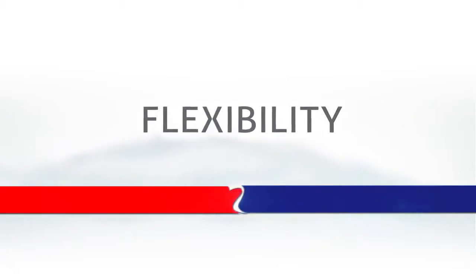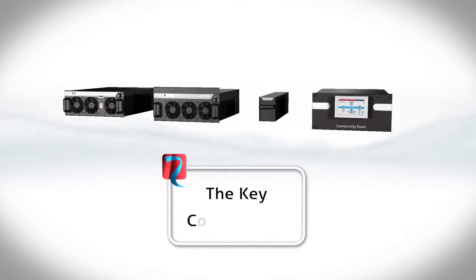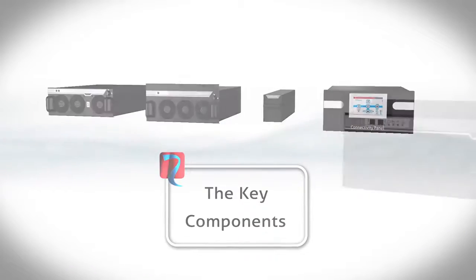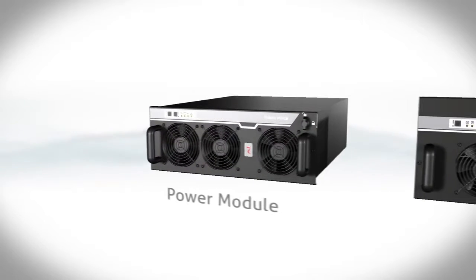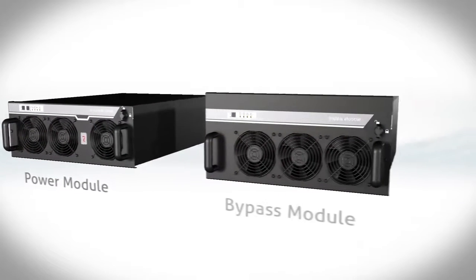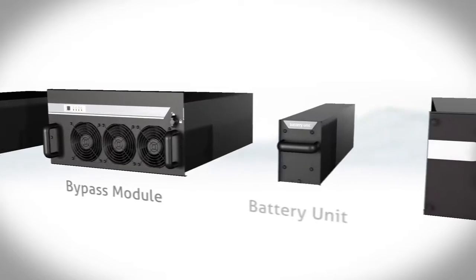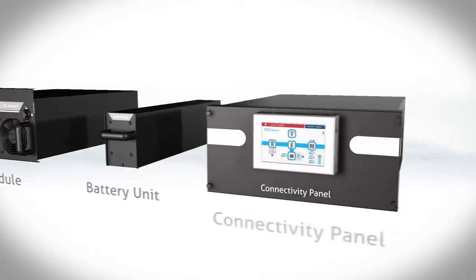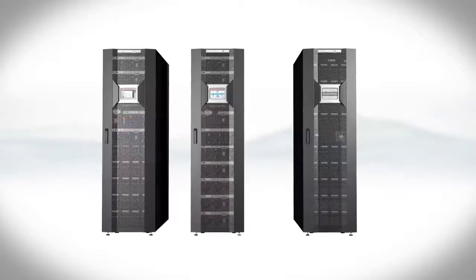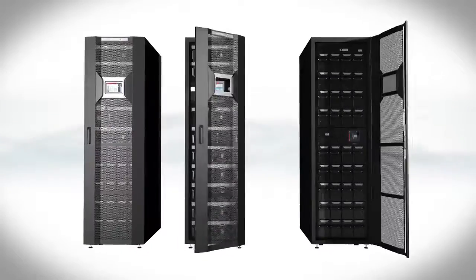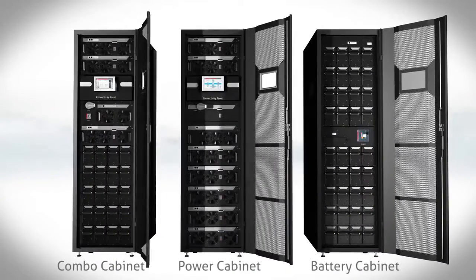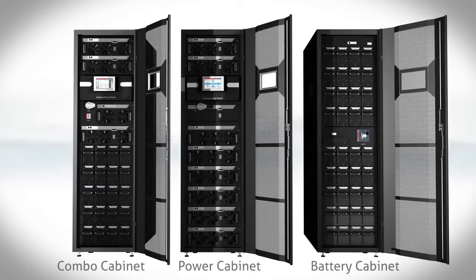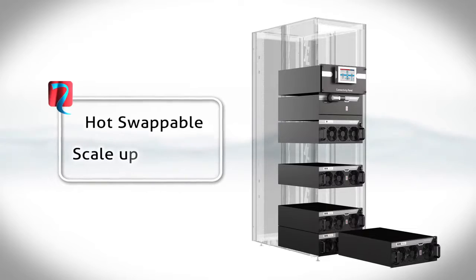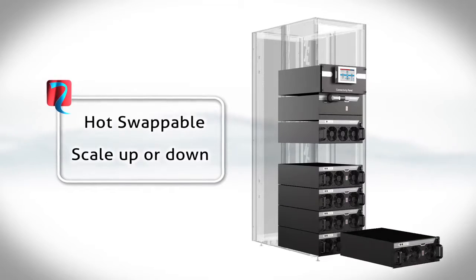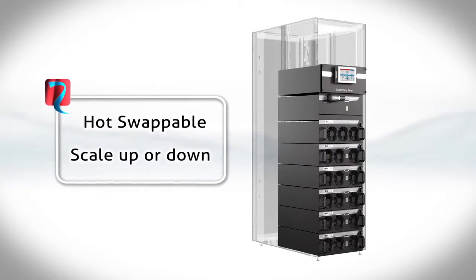Flexibility. To achieve maximum flexibility, we have separated the major parts of the UPS into its key component systems to ensure complete modularity. Power module, bypass module, battery unit, and connectivity panel. A stylish range of cabinets house these modules to enable flexibility of installation and service. The main benefit of this feature was to ensure the modules were hot swappable, allowing painless scaling up or down or replacing as required, without the need to power down and affect the critical IT load.